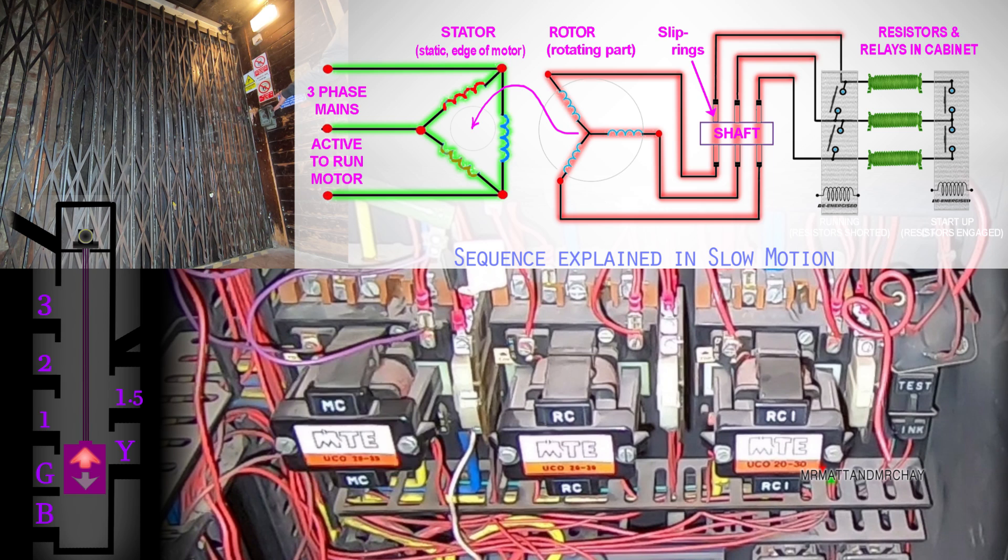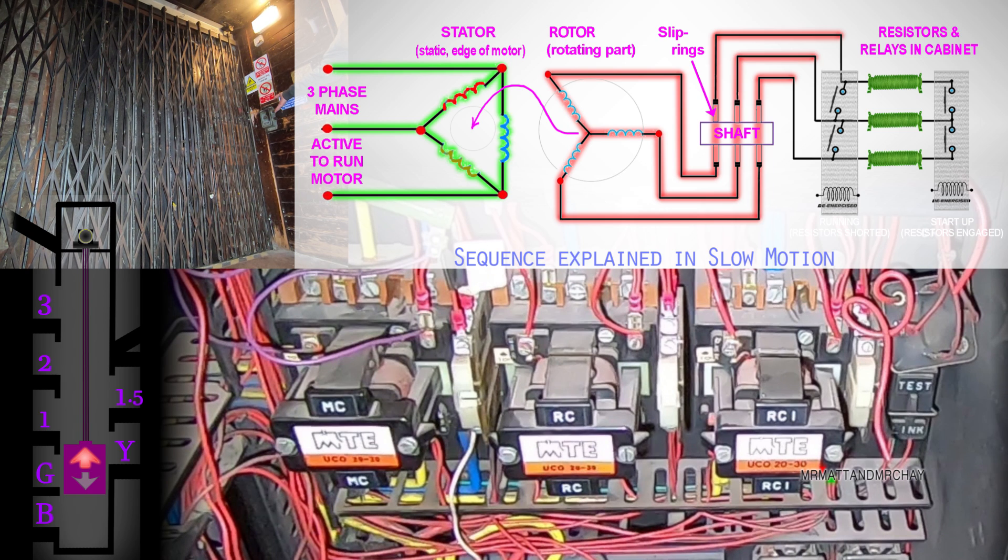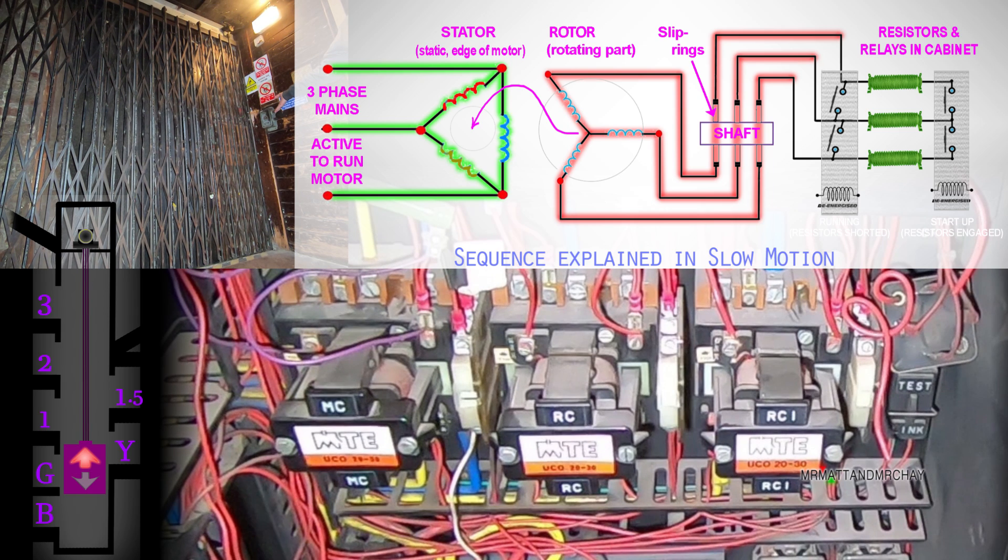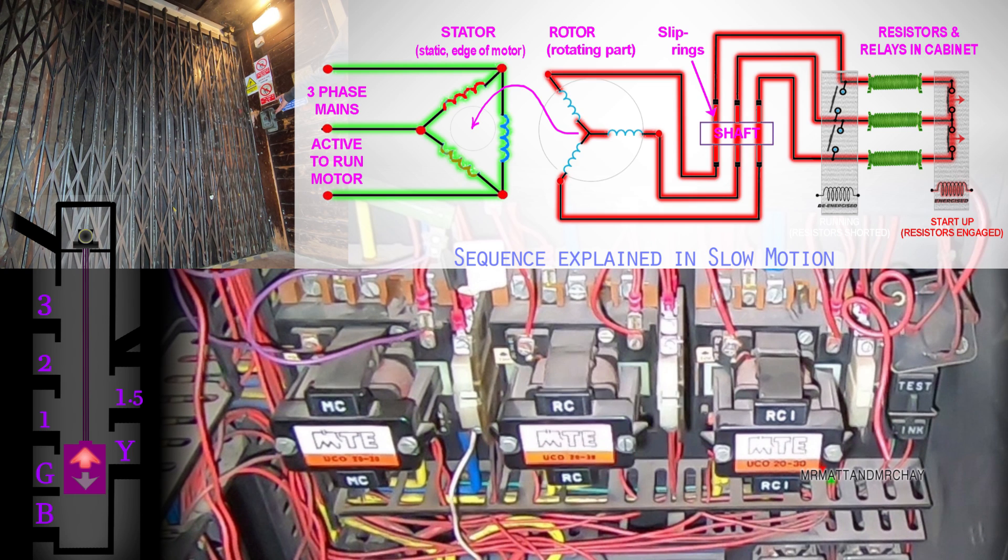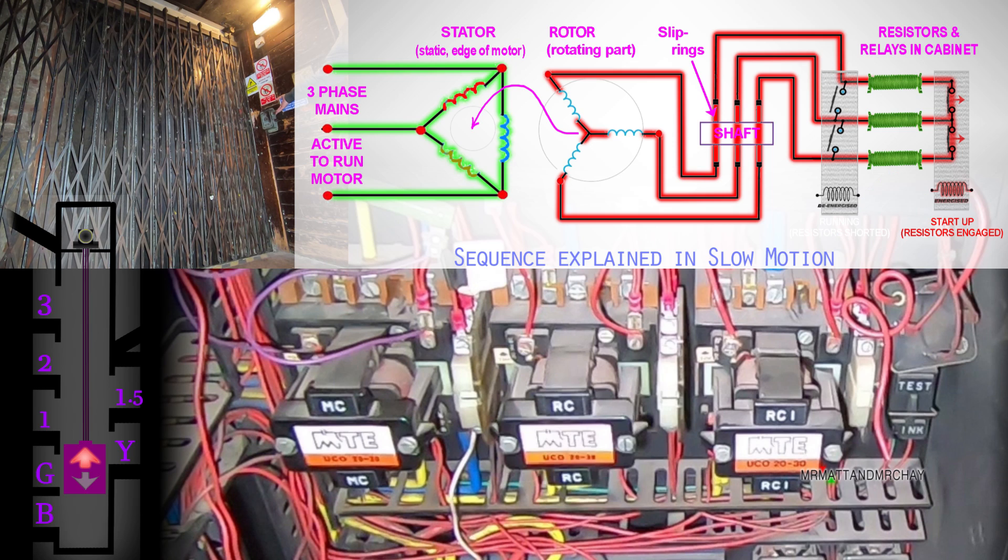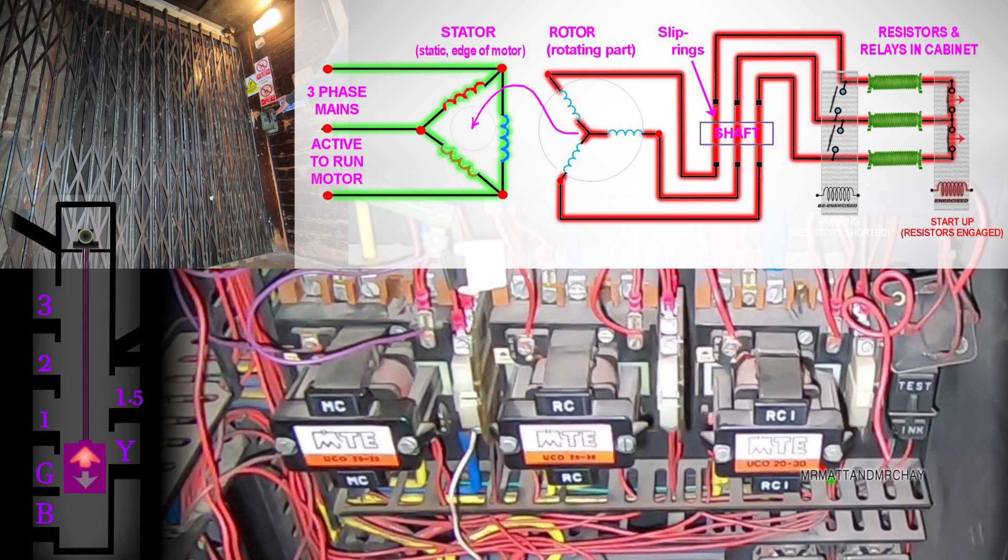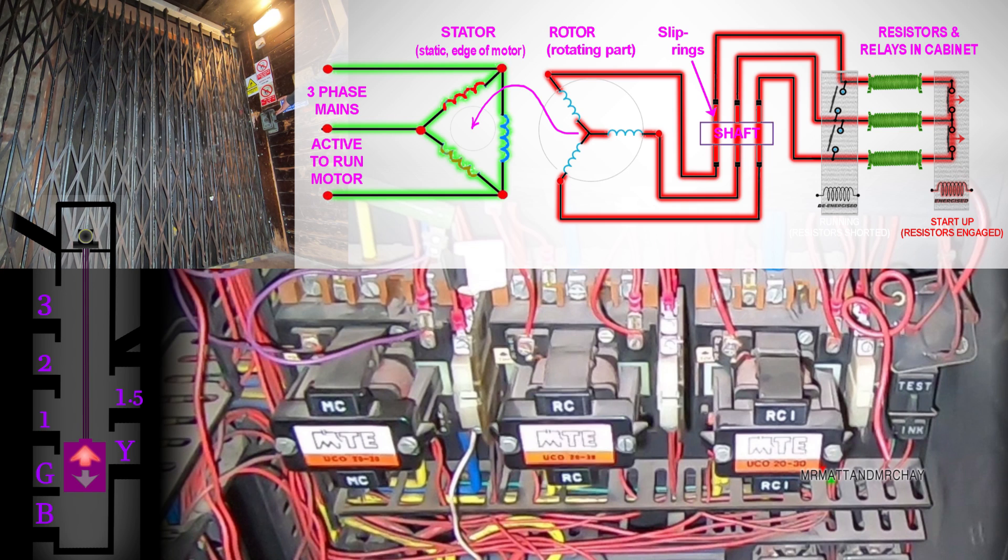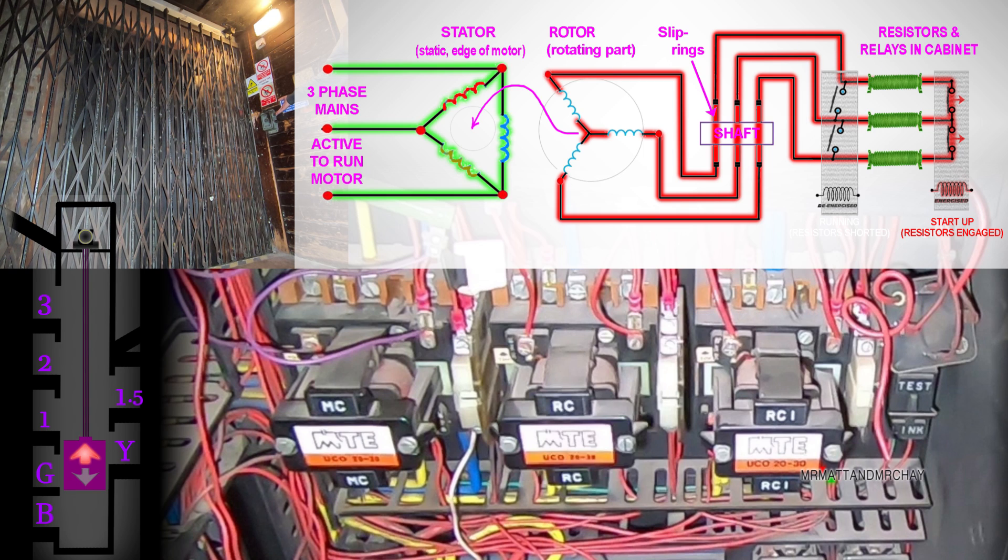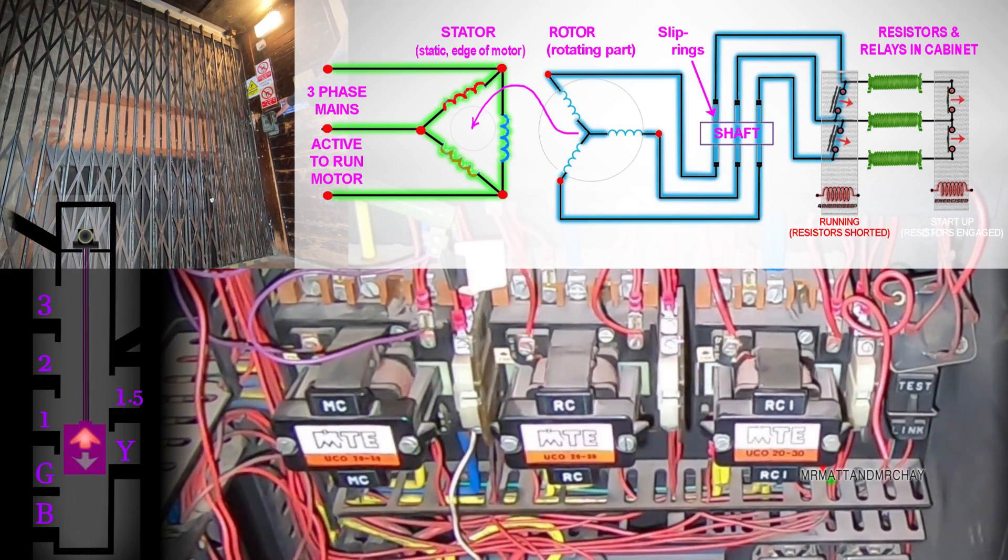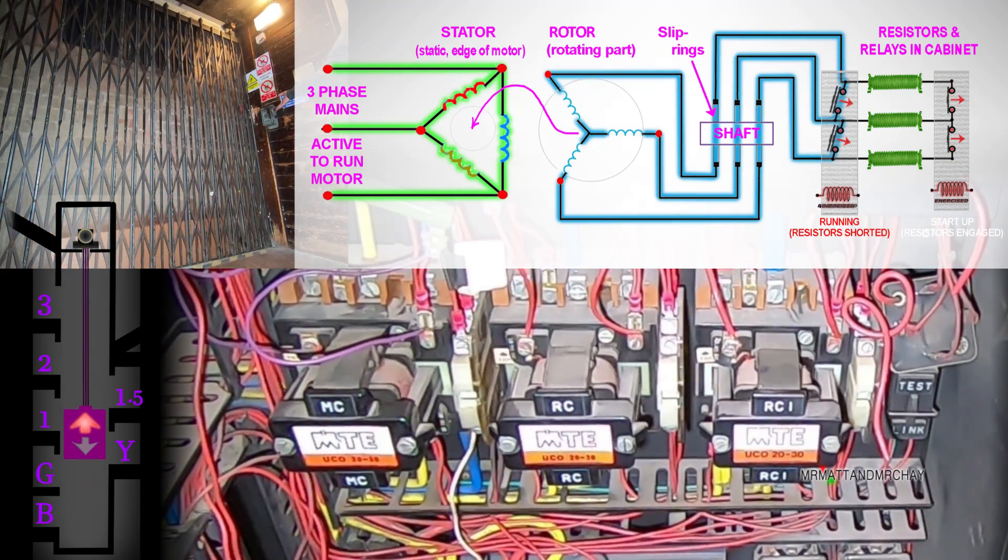Once the stator has power, the rotor is ready to turn. One and a half seconds later, the RC contactor connects all windings together, but forcing them through three resistors. This limits the amount of current being shared from winding to winding, creating the torque or magnetic grip advantage to get the motor running. One and a half seconds later, RC1 contactor creates a short circuit before the resistors, shorting them all out. This creates the conventional caged motor configuration for normal running.